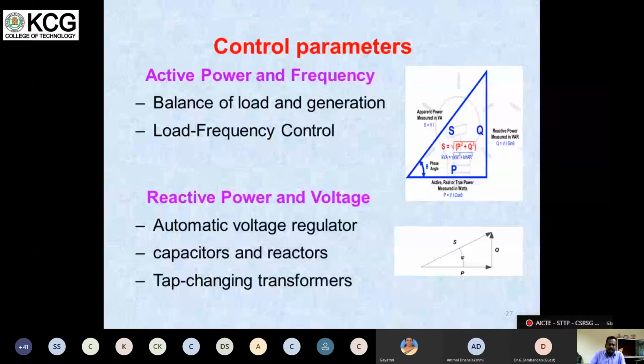Active power controls the frequency. If the active power supply is lesser, then frequency will be lesser. If active power is more, then frequency will be more. So it shows the balance of load and generation. If the load is lesser and generation is more, it leads to higher frequency. If generation is less and grid load is more, it leads to lesser frequency.